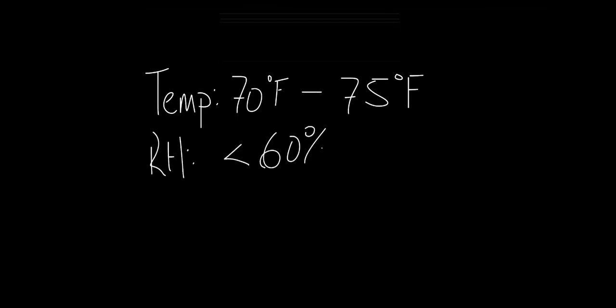For patient rooms, standard 170 requires the design temperatures to be between 70 and 75 degrees. Relative humidity must be maintained below 60 percent.